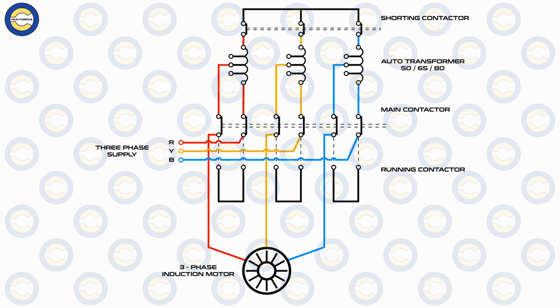Now, typically in the design, there are two types of designs. One is the fixed tapping. In this type, which is mostly available on board, the transformer is supplied with predefined tap terminals. During the installation or the maintenance part, the electrical officer can also choose the tapping to which they want to connect the outgoing lead. But once selected, the ratio remains fixed during normal operation.